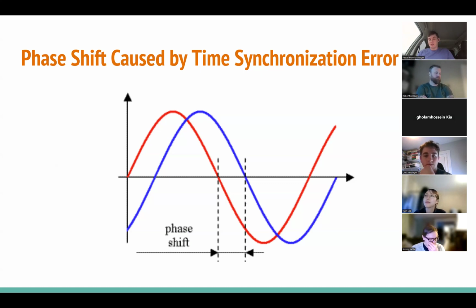In a conventional substation, we're not comparing analog signals to that degree of specificity, so we only need time accuracy to about 1 millisecond—1,000 times less accurate. That's why we can use older technology like IRIG, the coax cable that goes to each IED. Conventional substations still use that, but it's still synchronized using a GPS satellite. It's just that instead of using our Ethernet network to bring the time signal together, every device needs its own coax cable going to it.